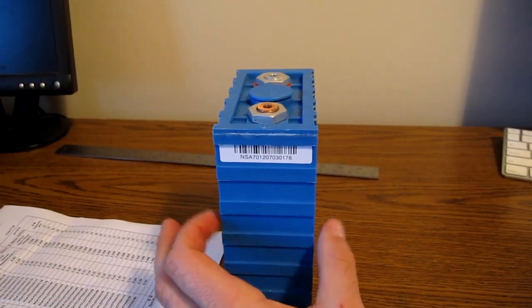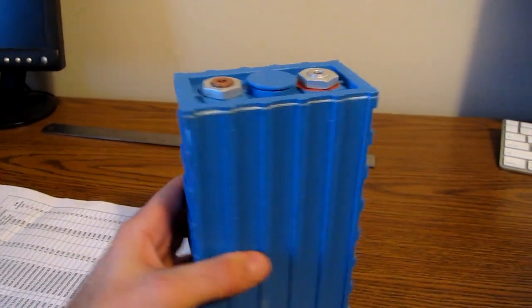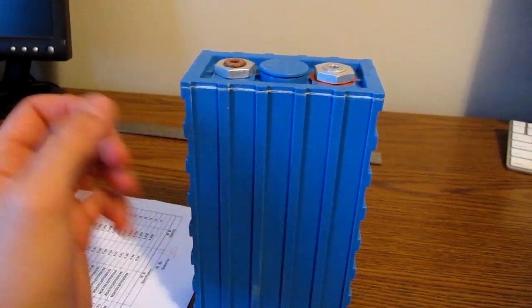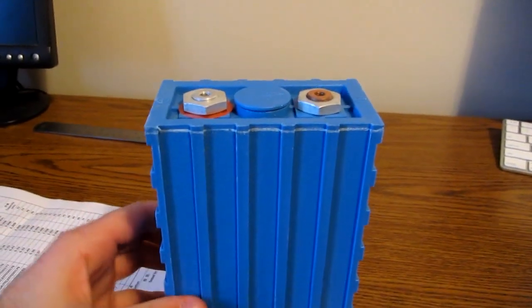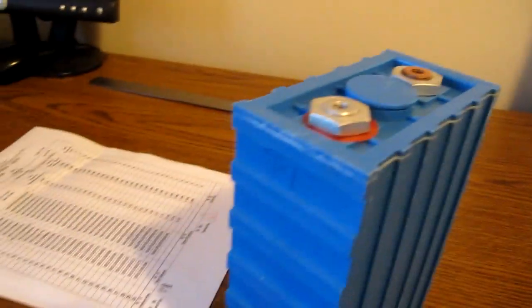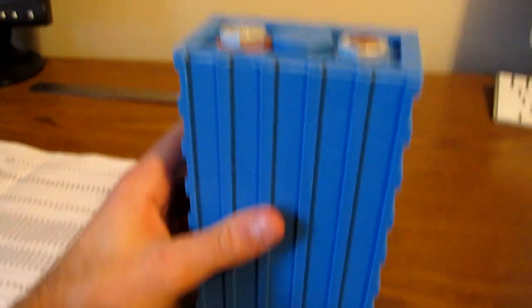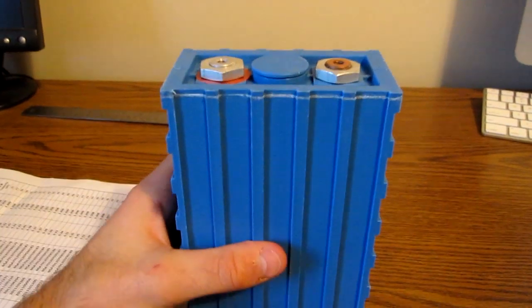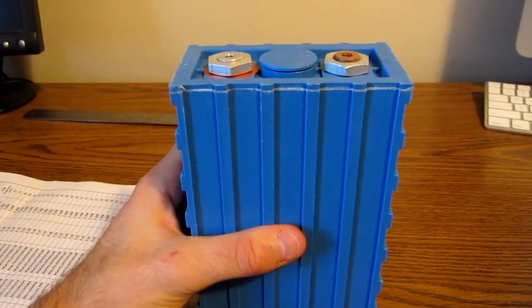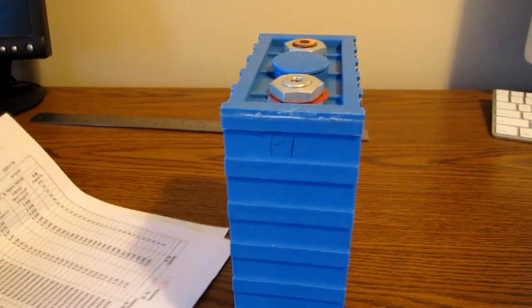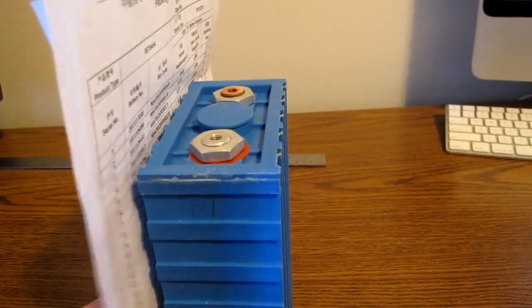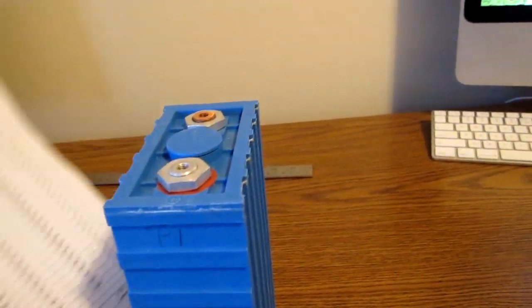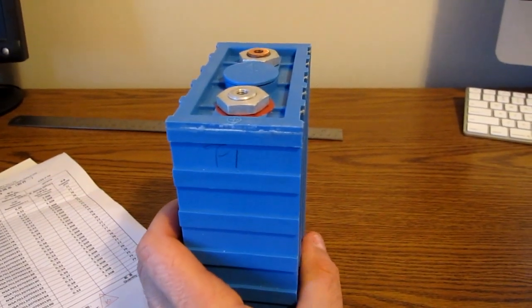What you really have to do when you install these batteries is you have to somehow restrict the movement of these large flat faces. The ends are not a problem, they're much shorter as well so they have more strength. The main problem is with these big broad sides, so you really got to somehow make sure that it's clamped so that it can't expand at all. If those plates separate then the internal resistance of your cell is going to go up and you're going to have capacity problems, discharge problems, and all sorts of problems. You really got to restrict the expansion of these cells.